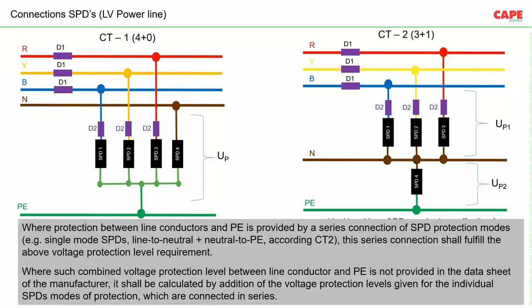Where protection between line conductors and PE is provided by a series connection of SPDs — in CT2, using single-mode SPDs line-to-neutral plus neutral-to-earth — this series connection must fulfill the required voltage protection level at the connection point, which is the impulse withstand capacity of the equipment. We must select the voltage protection level as the sum of UP1 plus UP2 plus the voltage drop across connecting wires, especially in 3+1 type connections.